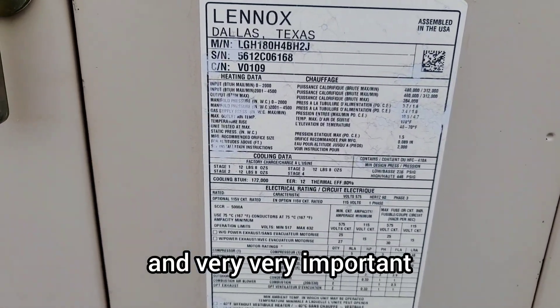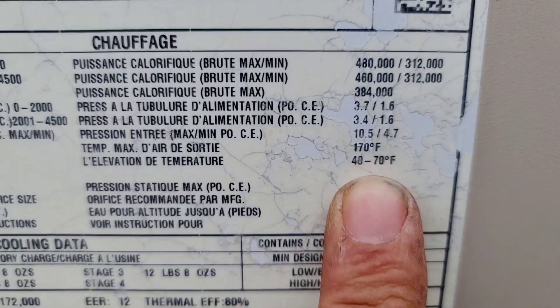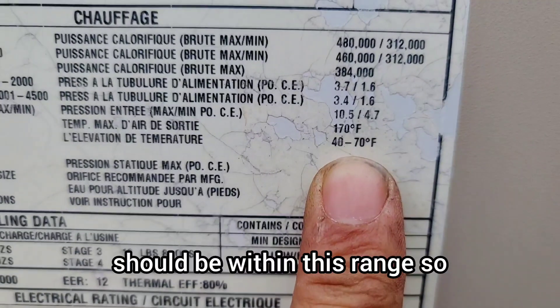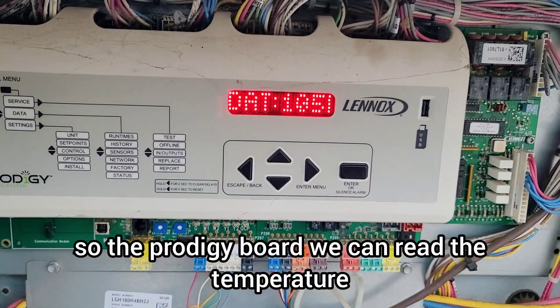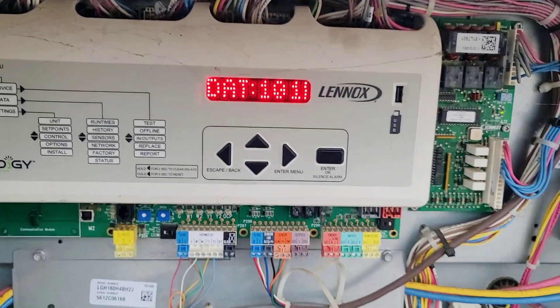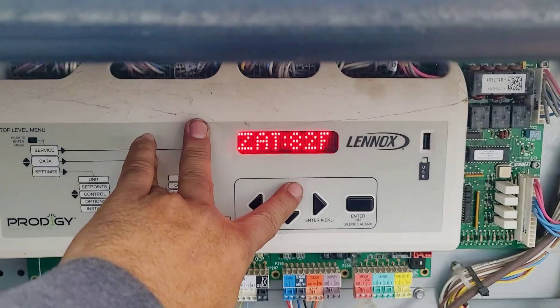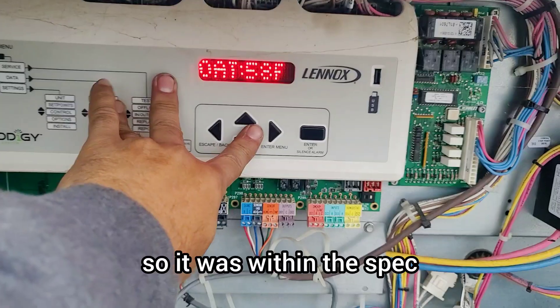It is very important during heating maintenance to check the temperature rise. Per the label, the range is 40 to 70 degrees Fahrenheit. The Prodigy board shows DAT — discharge air temperature — at 101°F, and RAT — return air temperature — at 84°F. The temperature rise is within the specified range.